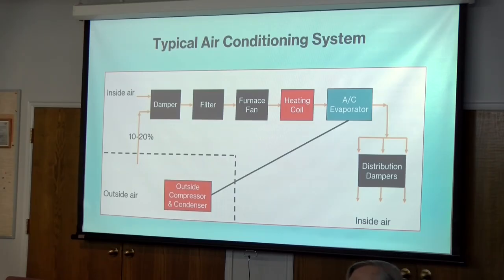Kind of six of one and half a dozen of another, depending upon the reason you're closing it off. Obviously, when you do that, you're reducing the total flow through your system. But if you have a good reason for doing so, then it's the right thing to do. At my house, I have one of those discharge vents going to a walk-in closet that we normally have closed off. If I had normal full flow going to that closet, it would get very warm in winter, and fairly cool in summer. So I choose to close off the damper and restrict the amount of flow going to that space, just to make it more balanced throughout, so we're not walking into a different temperature as we go in and out of the closet.